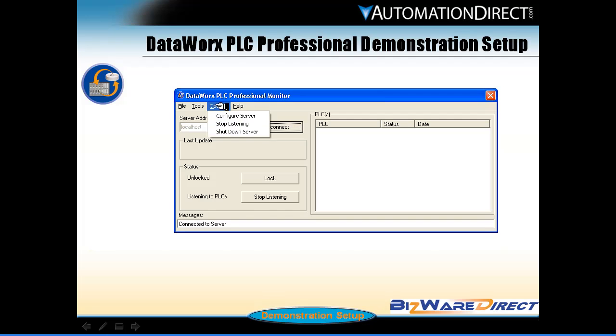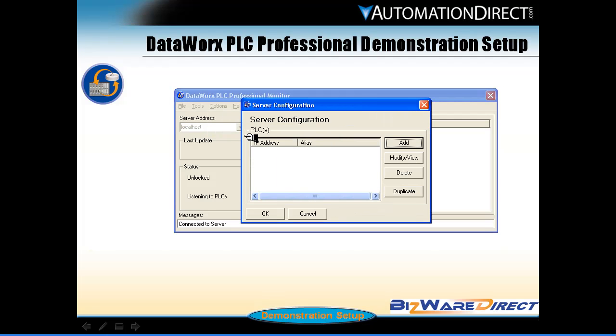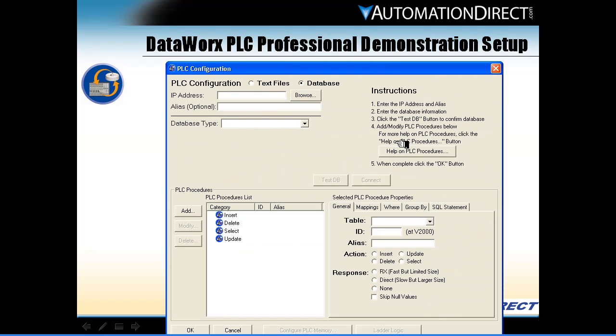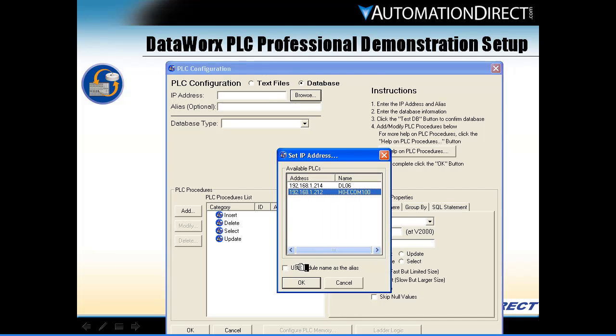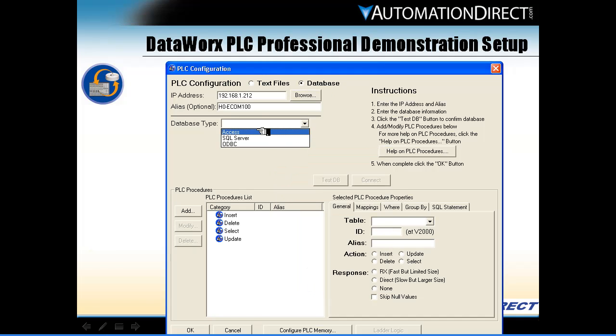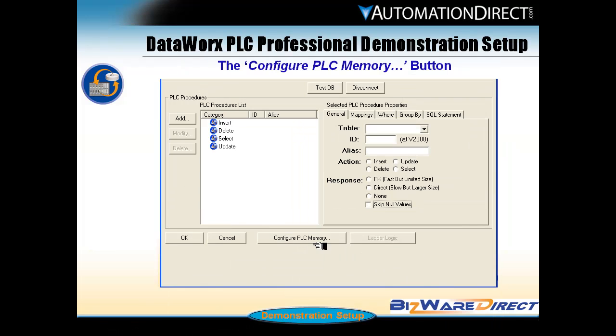Choose the Options menu, select Configure Server, and click Add. The PLC configuration window will open. Type in or browse for the PLC IP address. Specify the database type. In our example, we are using a Microsoft Access database. Browse to or type in the file name path. Our database is called plantoperations.mdb. Click Connect. Now that we have established a connection with the target database, let's configure the PLC memory.